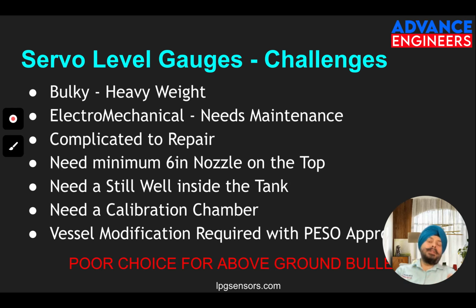Now, with LPG, when there is a filling of the tank, it's always from the bottom. So there you will see there is a lot of bubbling coming up on the top. There are a lot of bubbles, or you can say turbulence on the top. Because of the turbulence, you will see the liquid moving, especially if these are bullets, and especially above-ground or mounded bullets, you can see the liquid moving from left to right or from front to back, depending on how the inlet is done. So the float also moves along with this. Suppose the float is at the center, and as soon as the filling starts and the liquid starts flowing to the other side, the float also goes over there.